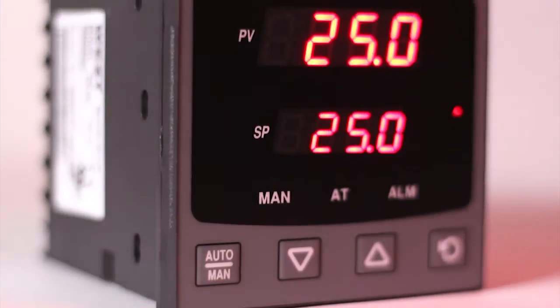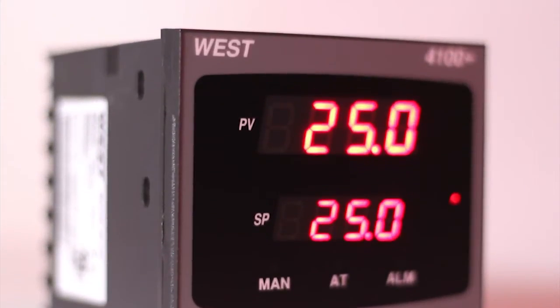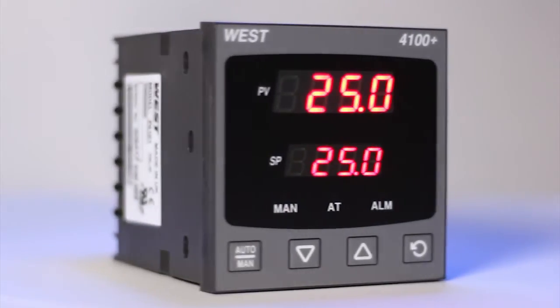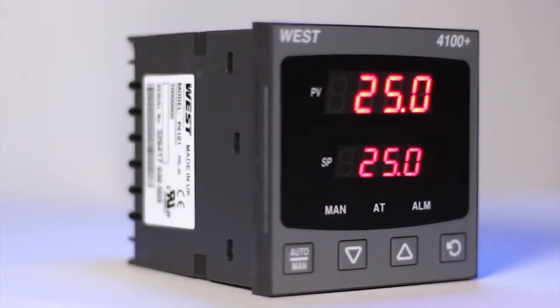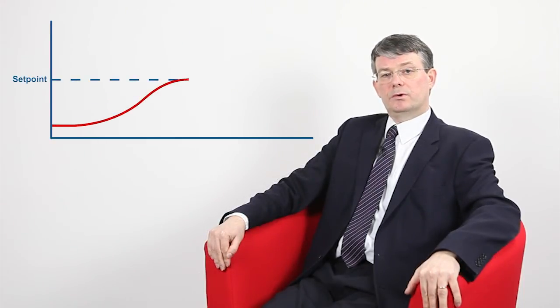Set point ramping is available on most of our controllers. It is used to protect the process or the equipment from quality problems or damage that may occur if sudden changes were allowed to happen in the process value. Without the set point ramping feature, any change in the set point would cause the process to be driven to the new value at the fastest rate that it was capable of moving.